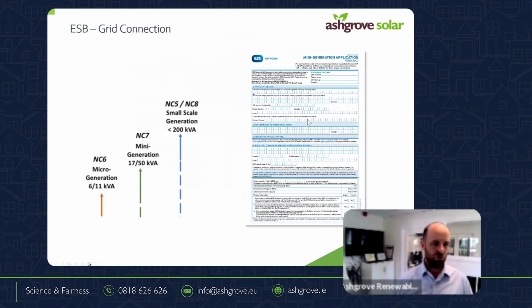What that application form looks like depends on the size of the system you're going for. There's a different form your electricity supplier should fill out - not necessarily you, but just so you're aware. The smallest form is the NC6, which we use on domestic applications all the time. It's basically a notification form - you submit it to ESB Networks and they acknowledge receipt. There's no real approval or rejection at that scale, but you can only put in a 5.5 kilowatt inverter, or an 11 kilowatt inverter at 3-phase. Those are the maximum sizes for that form.